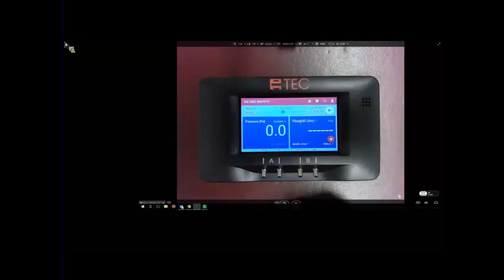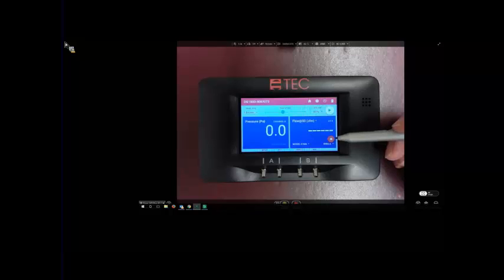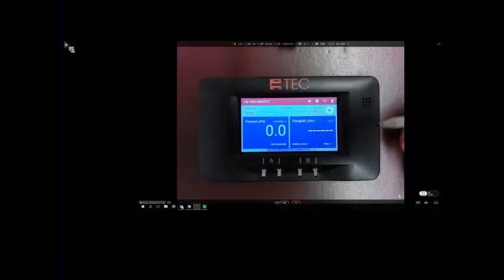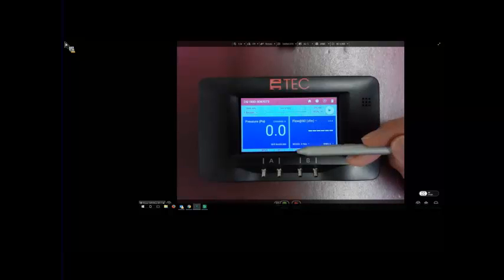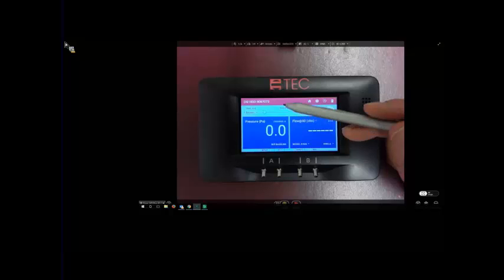We have the fan speed slider, so you can manually adjust what you want the fan speed to go to. So we can turn it on. You can see it's responsive, moving back and forth. If I leave it in place, you'll notice that there is now a stop button that shows up on the screen. And when I push the stop button, you see fan stopped, and the fan speed slider went all the way to the bottom.